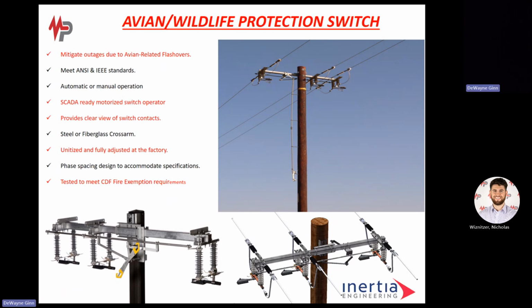These are tested to what we call the California fire exemption requirement. Basically, the test is, you have very highly combustible material you put down on the ground, and you put the pole into that material and put the switch on the pole. And you put fans onto that material to blow on it in case there's sparks that fly down and it could create a fire. You energize the switch and open and close it, I believe it's 10 times. So if there's any arcing or sparking coming off that switch, it would fall down into the material and create a fire. Again, we passed this with our switches, and it's a published document that the California fire exemption, I believe it's called CDF, publishes every year.